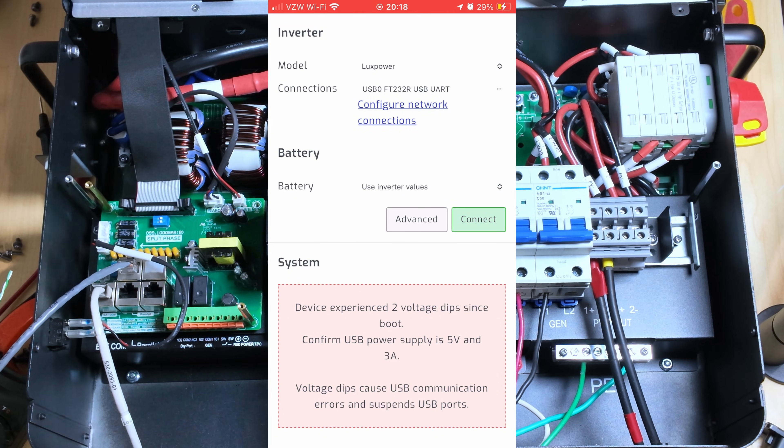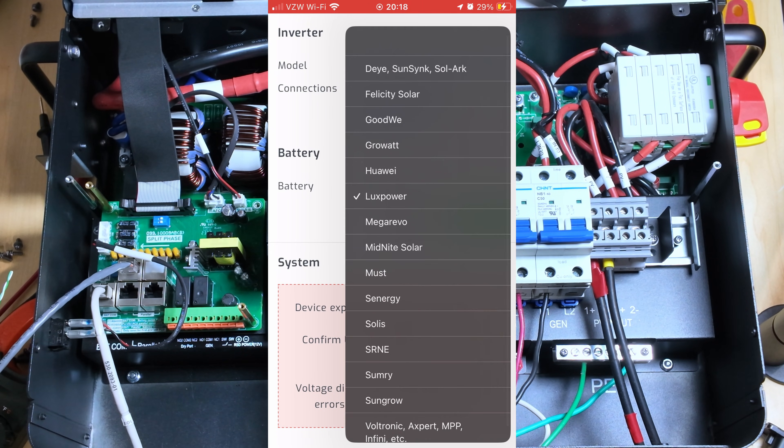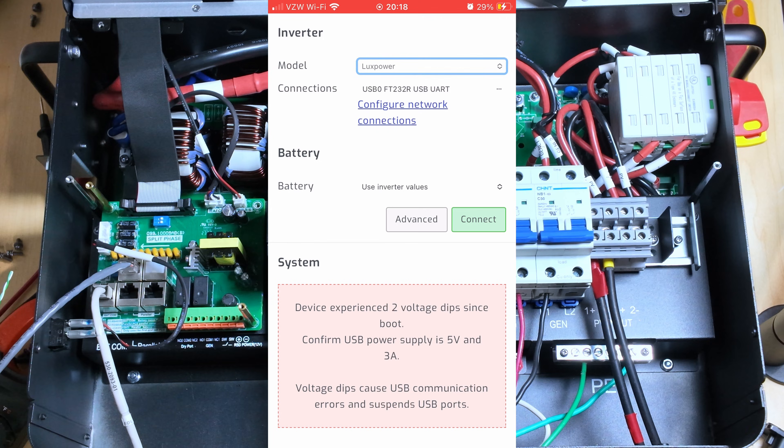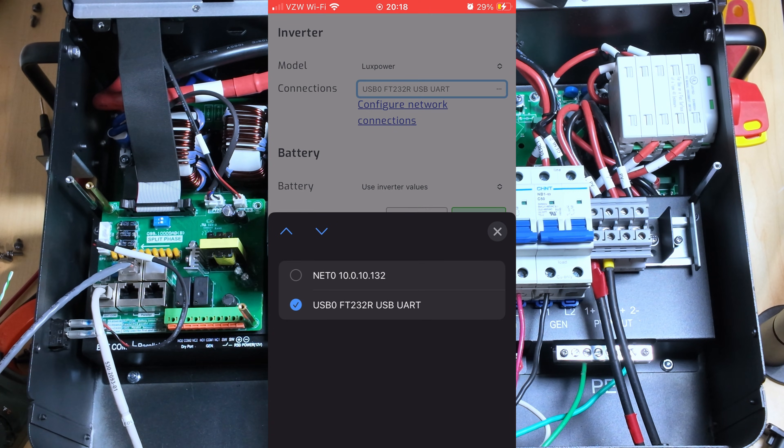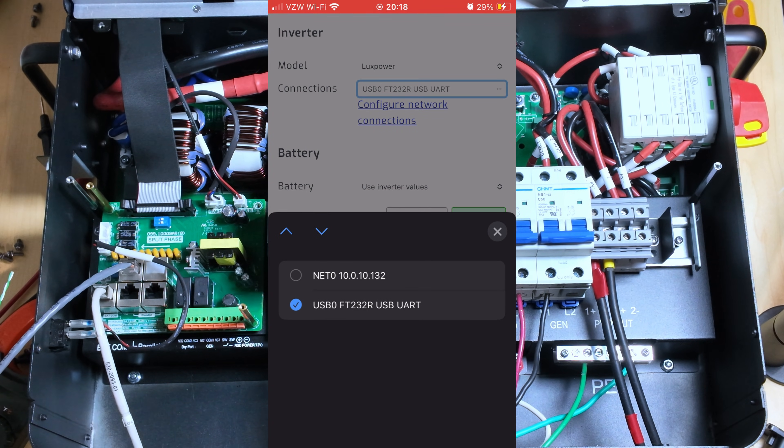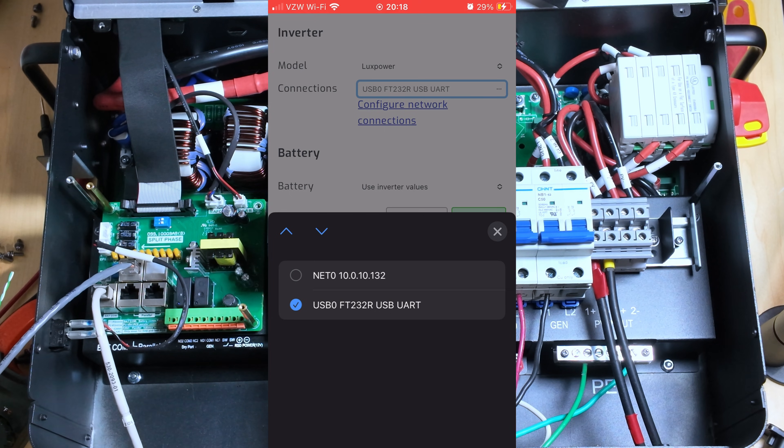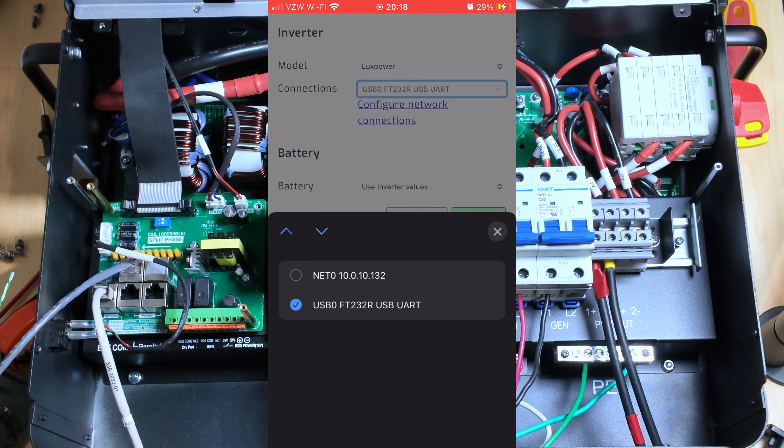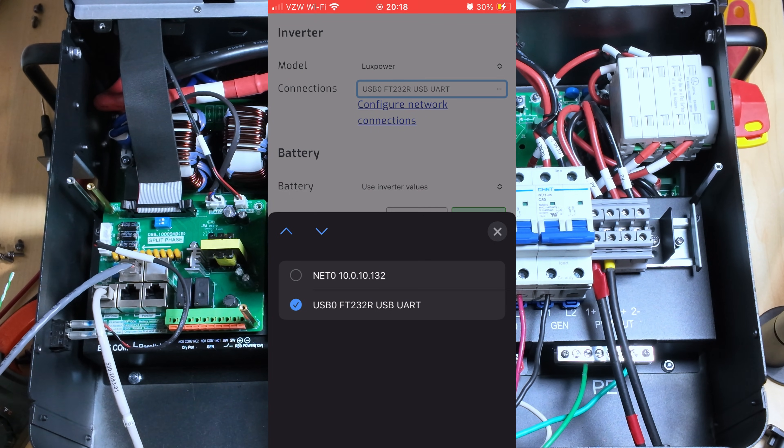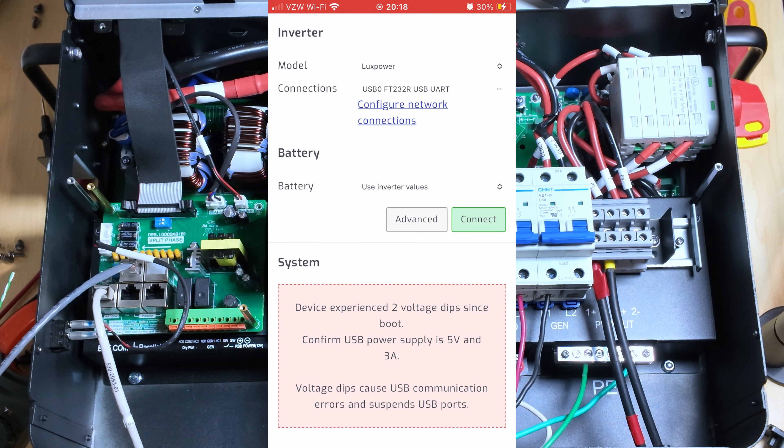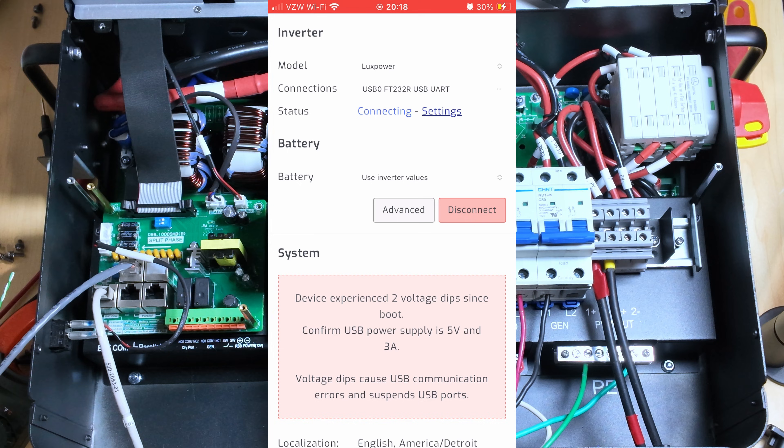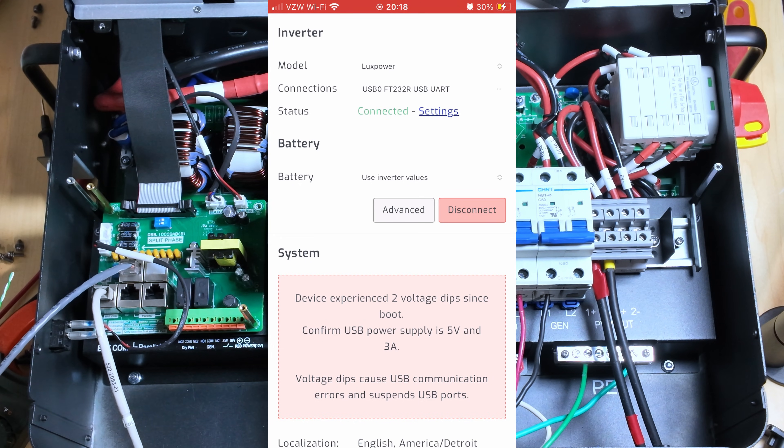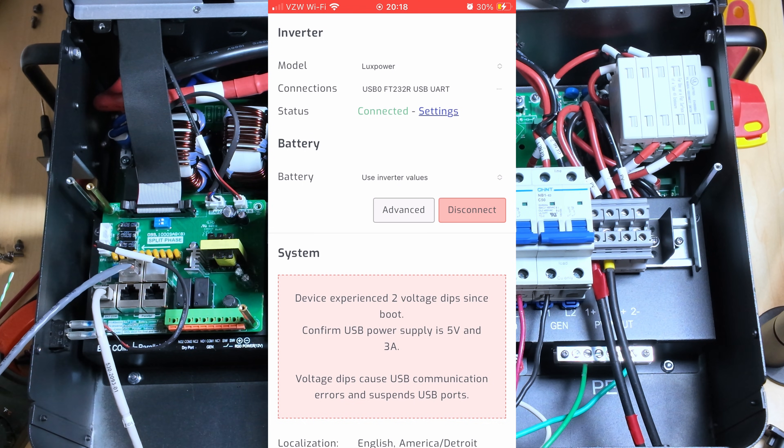So here I am in Solar Assistant on the configuration page. We select LuxPower. And in the past, you can see I have Net Zero for a wireless network connection already configured. But I switched it to that USB to RS-485 cable. And then I hit connect. Discovered address 1. And then it went connected.